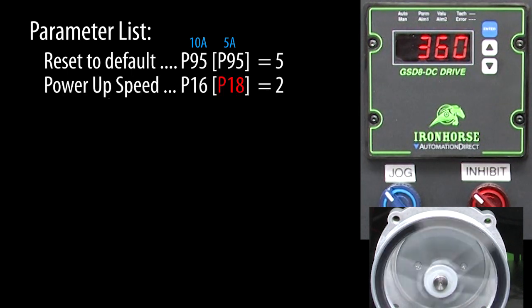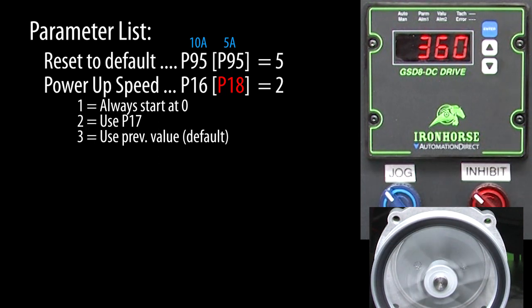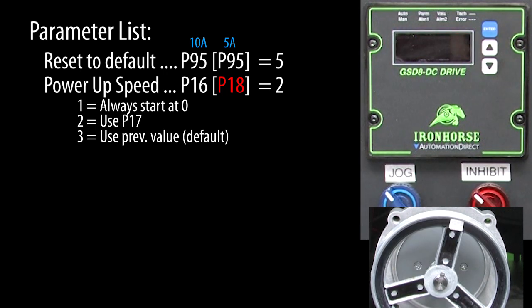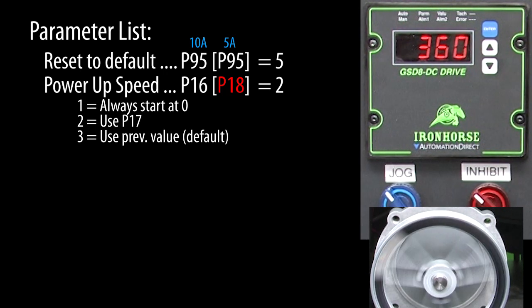Do you want the drive to automatically run when the power is applied or do you want to manually ramp it up to speed like we just did? You actually have three options via parameter 16: always start at 0 RPM, always use whatever is in parameter 17, or use the last entered value. The drive defaults to use the last entered value, so if I power down, give it a second, and bring it back up, sure enough it picked up right where we left off.